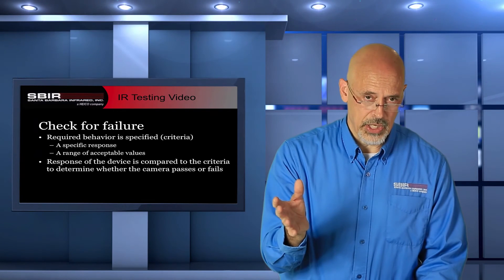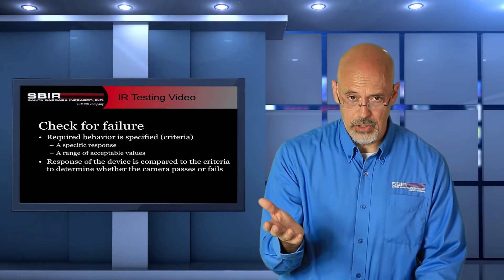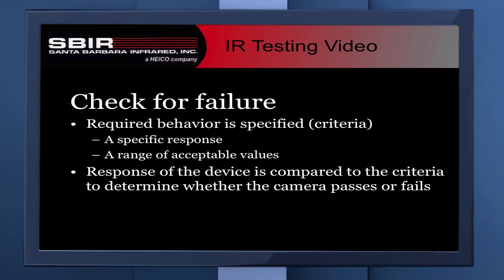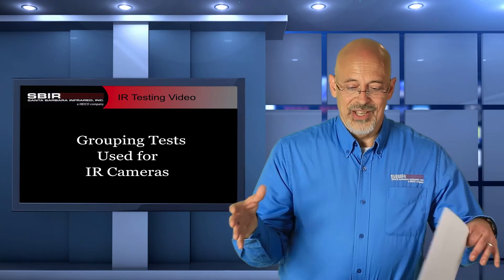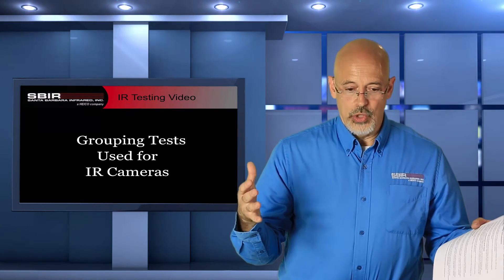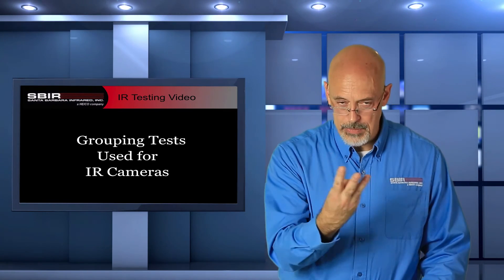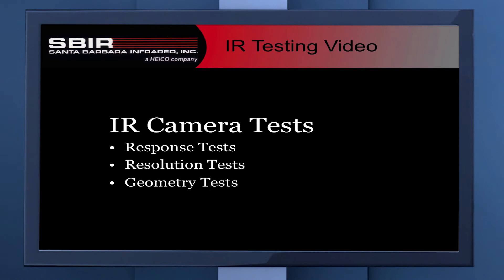The third reason you'd be doing testing on a camera is checking for failure. This is generally when you're out in the field — you have a camera that is going to be used in some critical operation, and you're trying to identify whether it functions properly before deploying or using it. Finally, tests are grouped into categories so you have a sense of what kind of equipment you're going to need. Infrared camera tests generally come in three different categories: response tests, resolution tests, and geometry tests.